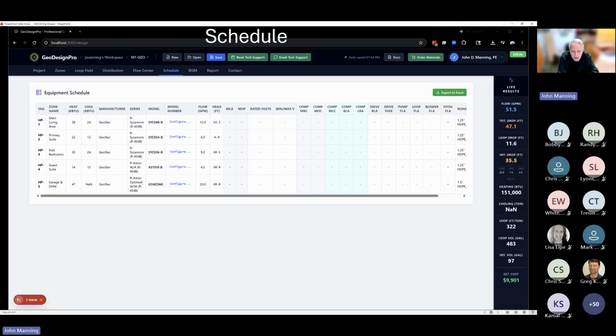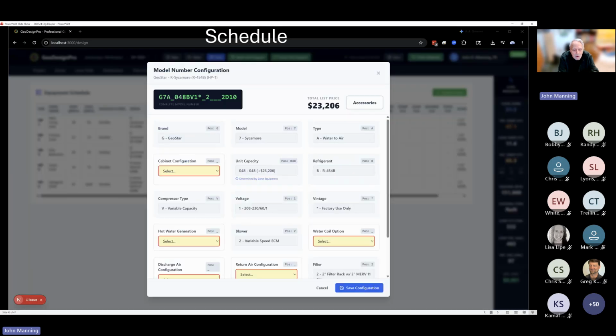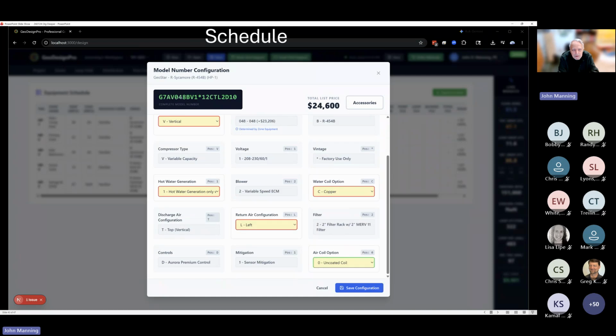Moving on to the schedule tab, this is where all the heat pumps are laid out in a schedule type structure. And one of the key elements is a configure button. You click on that, and now you get to define the heat pump in virtually every detail that the manufacturer offers. So you go through and define whether you want copper or cupronickel heat exchangers, whether you want a hot water generator or a desuperheater, whether it's a vertical or horizontal heat pump, and so forth. You go through that process, it completes the model number, so there's no ambiguity about what you're specifying. It also brings up a list price of that particular configuration.